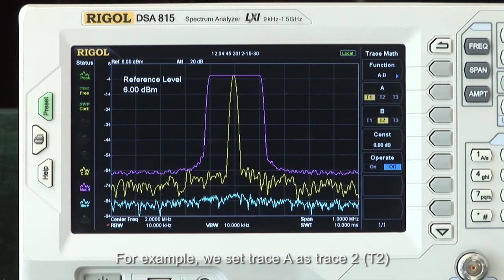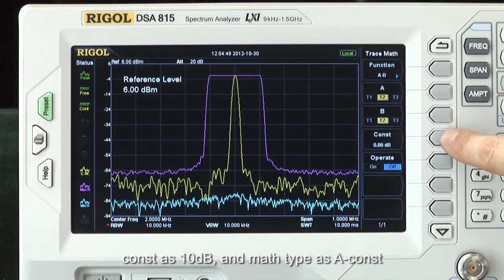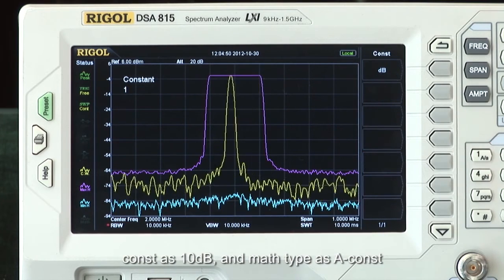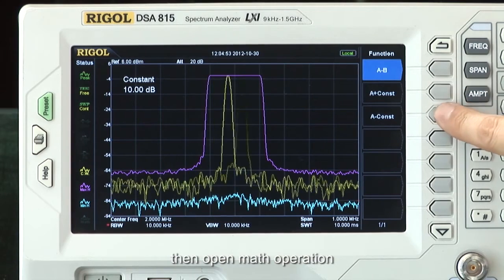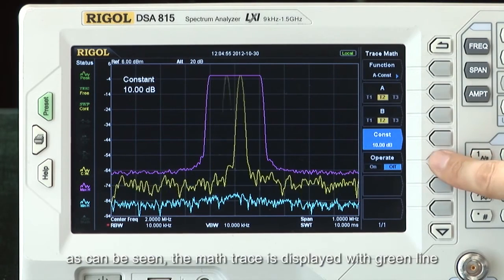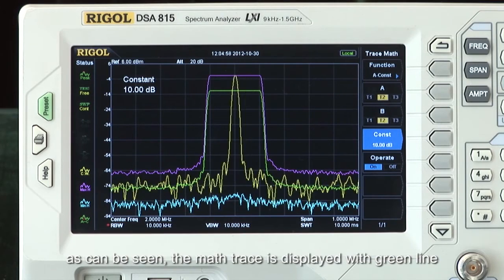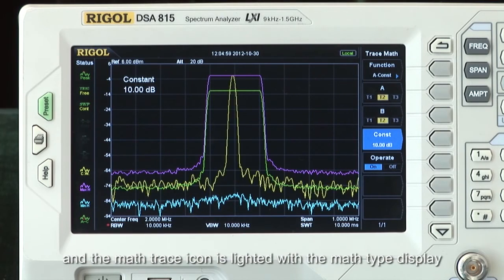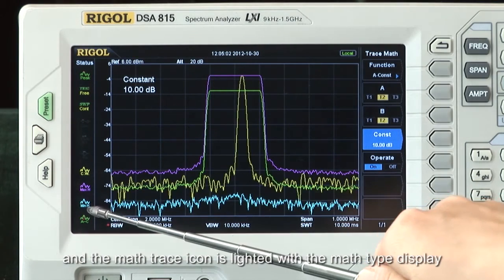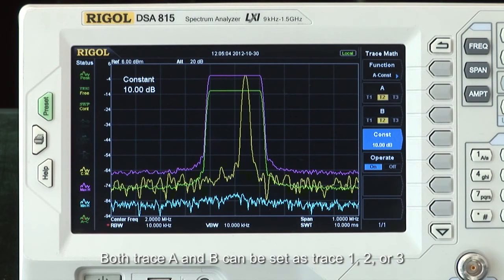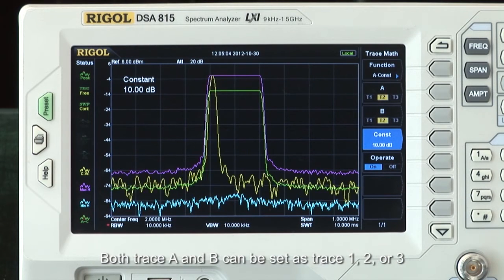For example, we can set Trace A as Trace 2, constant as 10 dB, and math type as A minus constant. Then open the math operation. As can be seen, the math trace is displayed with a green line, and the math trace icon is lit with the math type displayed. Both Trace A and B can be set as Trace 1, 2, or 3.